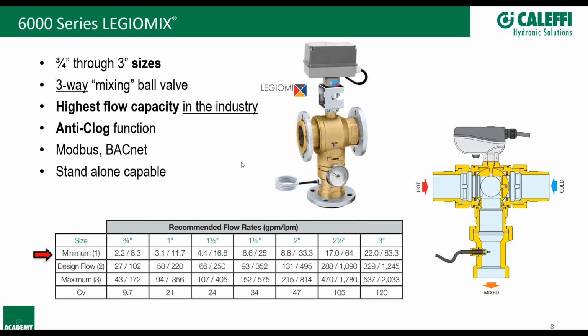Yeah, so with a globe valve, in a lot of cases, you're going to have a lot more issues with scaling and seizing, because typically that globe valve is going to be run by some type of stepper motor on the very top of it. The idea is that it can go full stroke, full hot to full cold, and it could clean off that stem that's being controlled by the stepper motor, but you're still always going to have that debris and potential for scaling on the actual disc that's doing the opening and closing to each side, so you might have a lot of issues there. And also in a lot of cases, those stepper motors have some pretty big clearance requirements as well.